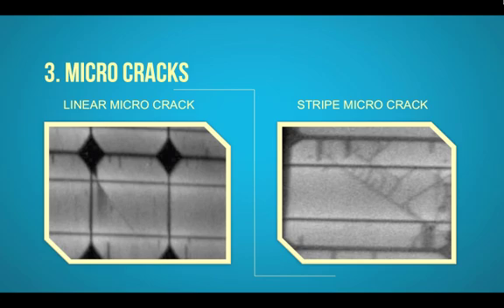During the manual soldering operation different thermal expansion of the copper and the silicon elements can occur at temperatures greater than 300 degrees. This temperature differential can result in the formation of micro-cracks in the cell and thus leading to higher cell resistance. Undetected micro-cracks can result in a less than expected field lifespan.